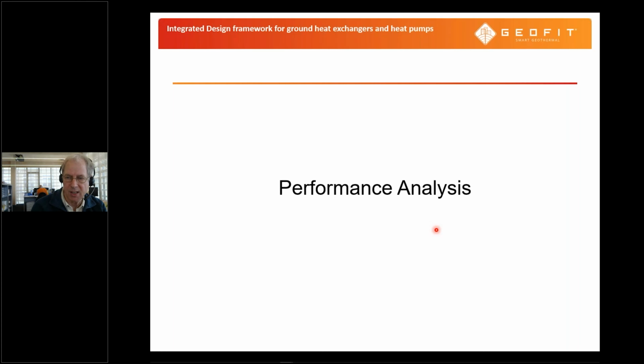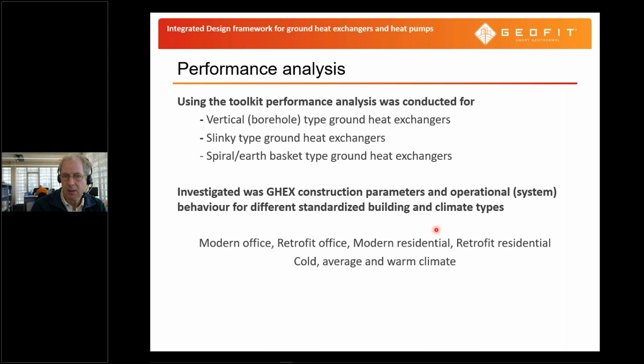different conditions. And then we're looking at construction parameters, but also at operational parameters. So the vertical borehole type, the slinky type, and the spiral earth basket type ground heat exchangers have been compared. And like I said, construction parameters and operational system behavior.